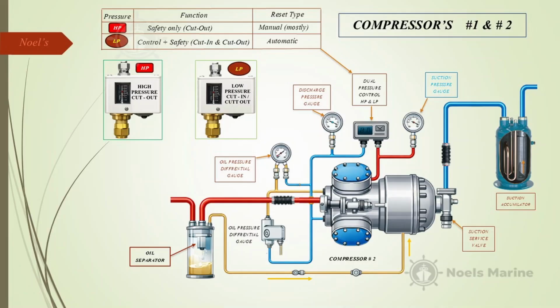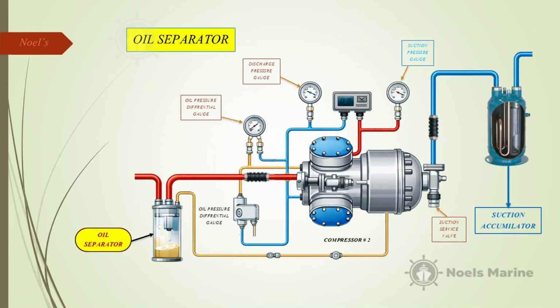Because during all that violent squeezing in the compressor, some lubricating oil actually escapes with the hot gas, right? It does. It gets carried away in the flow. And you do not want oil coating the inside of your heat exchangers down the line. It acts as an insulator and ruins your efficiency. So how do we fix that? We use an oil separator. It's placed right after the compressor.